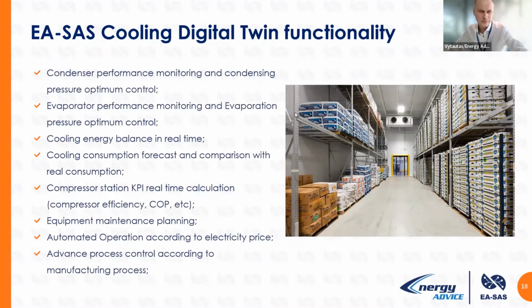First, we monitor condenser performance, and of course have an effect on condensing pressure optimization. Also operation side and operator efficiencies, cooling energy balance in real time, cooling consumption forecast and comparison with real consumption, compressor station KPI. And we also calculate compressor efficiency by itself, so we can check whether a compressor, as a device alone, is working at a good efficiency point.